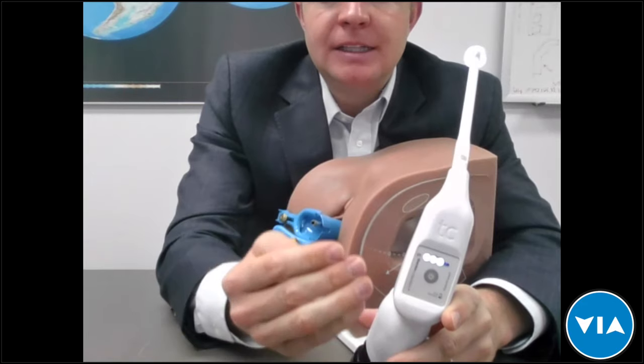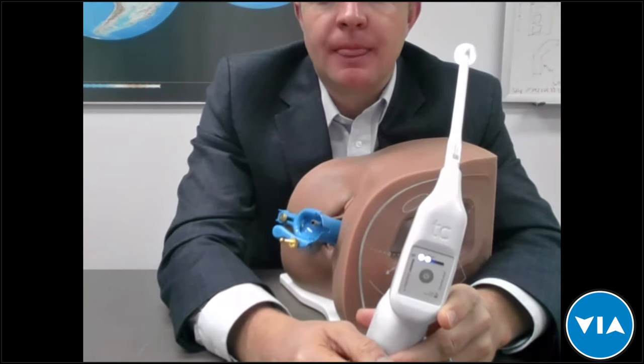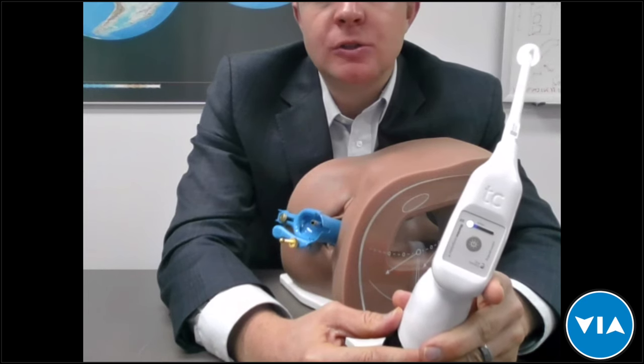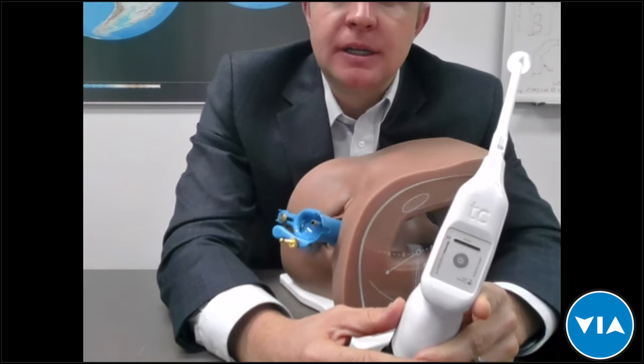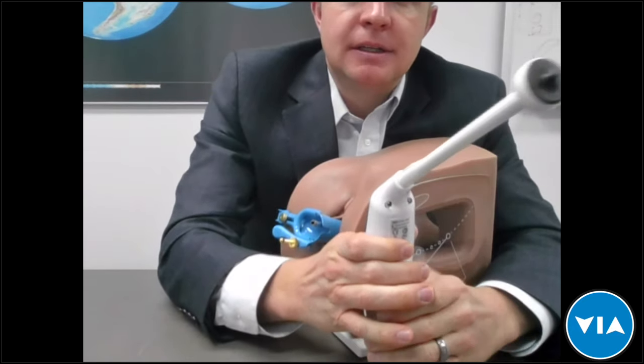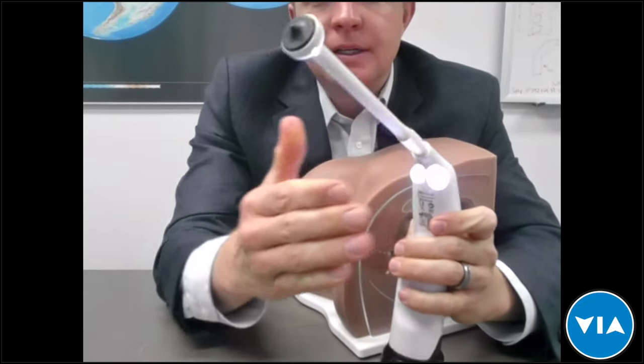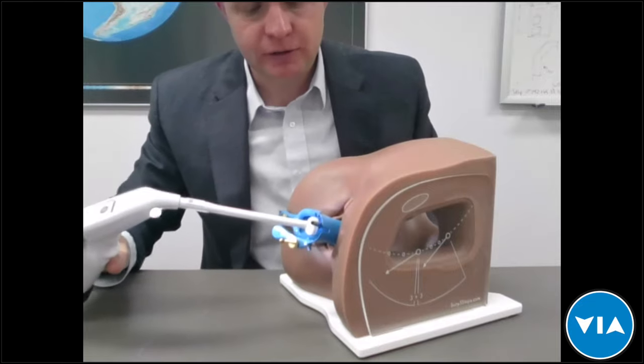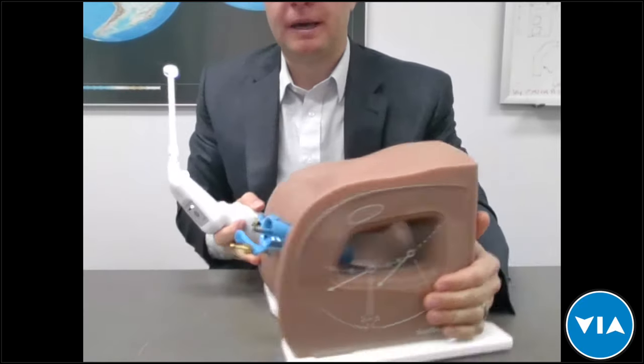Pressing the button a second time starts the heating. The unit is set to 100 degrees Celsius for a 30-second treatment, taking about nine seconds to heat up. Once at temperature, all four lights are on. The lights and beeper count down for the user — about seven to eight seconds between each light or beep — telling the clinician how long the treatment is going and indicating to the patient how therapy is progressing. The device is inserted intravaginally, typically used with a speculum to open the vagina for visualization and insertion.